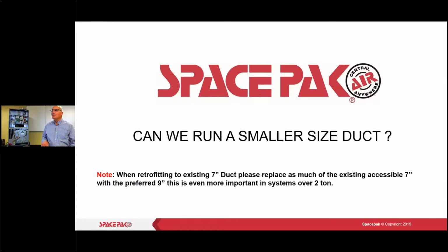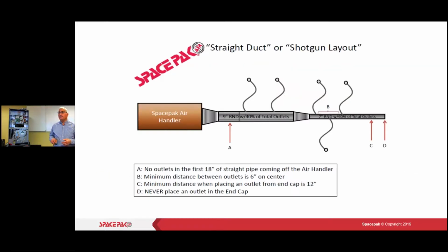All right, so can we run a smaller duct size? Retrofitting to that existing 7-inch, I kind of alluded to that earlier. What does it say? Please replace as much of the existing accessible 7-inch with preferred 9-inch. This is even more important in systems over 2 ton because we're moving so much air at a high speed, which is going to cause us a problem. So depending on what we're doing, the first 18 inches is minimum, always has to be 9-inch.